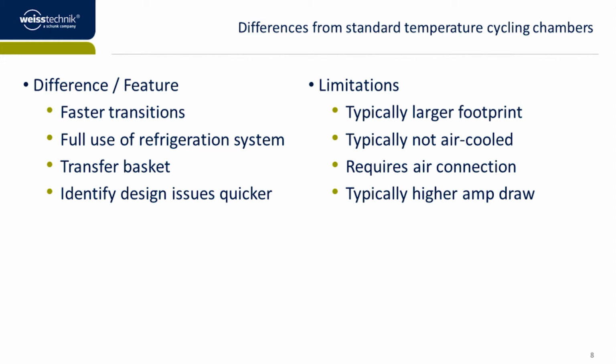The limitation on that is thermal shock chambers will typically have a higher amp draw. For a standard temperature cycling chamber, you'll cool it, the refrigeration will turn off, then you'll heat it, the heaters will turn off, and you'll repeat.